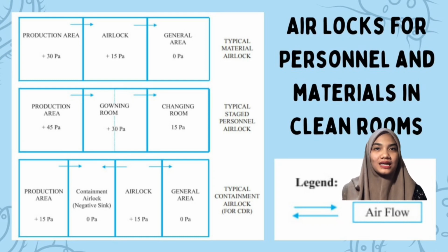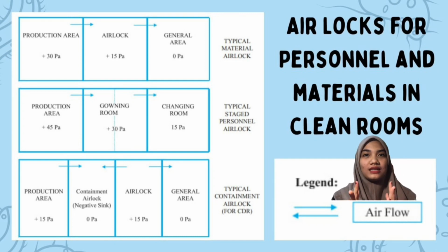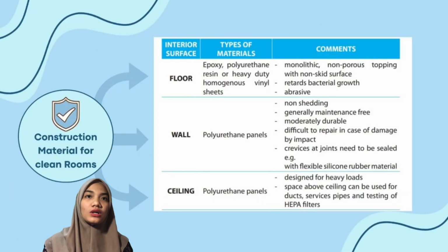Moving on to the personnel airlocks, pressures are meticulously set at 45 Pascal in the production area, 30 Pascal in the gowning area, and 15 Pascal in the changing room. The progressive reduction in pressure, coupled with the controlled airflow from the production to the gowning area and then the changing room, ensures systematic containment of contaminants. Lastly, in the containment airlock, pressures are different, which are 15 Pascal in the production area, 0 Pascal in the containment airlock area, and 15 Pascal in the airlock area. This tailored pressure arrangement, along with the airflow from the production to the containment airlock and then the airlock, safeguards the environment.